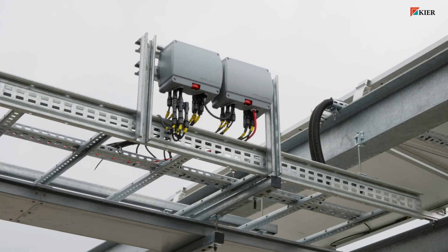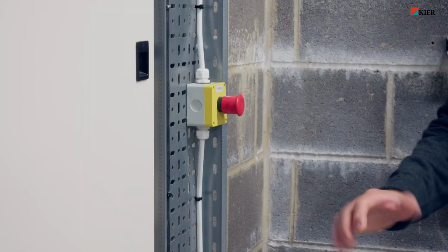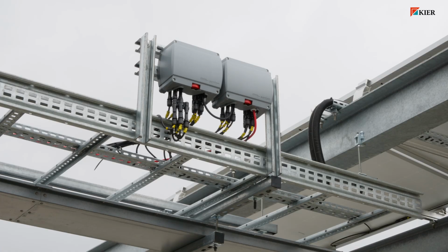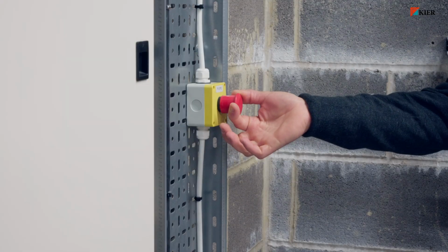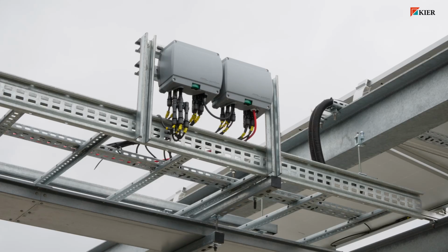We're demonstrating the set of fireman switches. These are activated via the EPO button inside the plant room. Once activated, they'll change status from red to green. Green indicates that it's now safe to work on the system. Once the EPO is reset, they'll change from green back to red, indicating that the system is now back live.